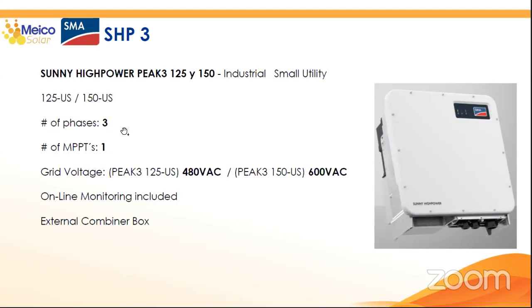The output is three phases. You only have one MPPT, and that's why this is only aimed for industrial and small utility, because when you have roofs with different orientation, different string lengths, shades, and all that, with only one MPPT, you can be in trouble for your generation. But if you have constant and homogeneous conditions for the modules, you can go directly with this inverter, more power, less inversion, and less cost of the equipment.